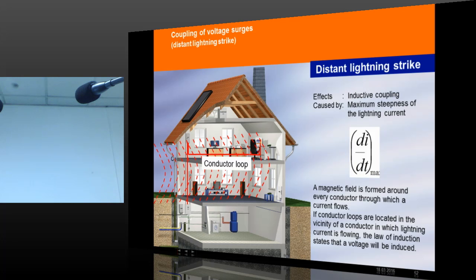What I explained is, in a distant lightning strike, electromagnetic force will flow over the area which will create surges in the conductor loop. One way of protecting the electronic equipment is to reduce the electromagnetic influence, these red semi-spherical lines. One of the ways of reducing the electromagnetic force is to create a Faraday cage in the whole building. And to create a Faraday cage, the best way is to interconnect the structural steel, which I explained in the previous slides.